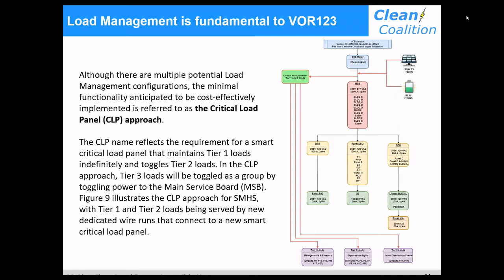The tier 3 loads in a critical load panel approach get toggled on and off as a group. They'll either be completely on - meaning power is served to them, whether they're actually operating depends on whether the light switch or appliance is turned on - or you turn them off as a block if you need to preserve the available energy for your tier 2s and tier 1s.